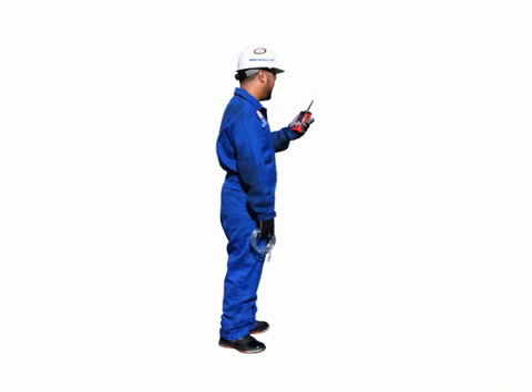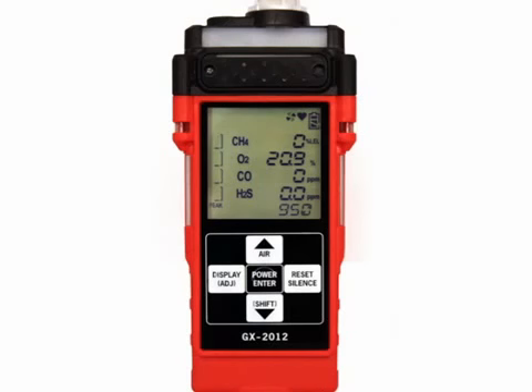There are three issues to keep in mind when monitoring for combustible gas. If your GX 2012 is equipped with both combustible sensors, then the percent LEL sensor will be exposed to combustible gas concentrations above its working range during monitoring and calibration. The GX 2012 provides the percent LEL sensor with protection against exposure to high levels of combustible gas. It does this by turning off the percent LEL sensor power temporarily when it determines that a percent LEL overscale, more than 100% LEL, concentration of combustible gas is present that may damage the sensor.